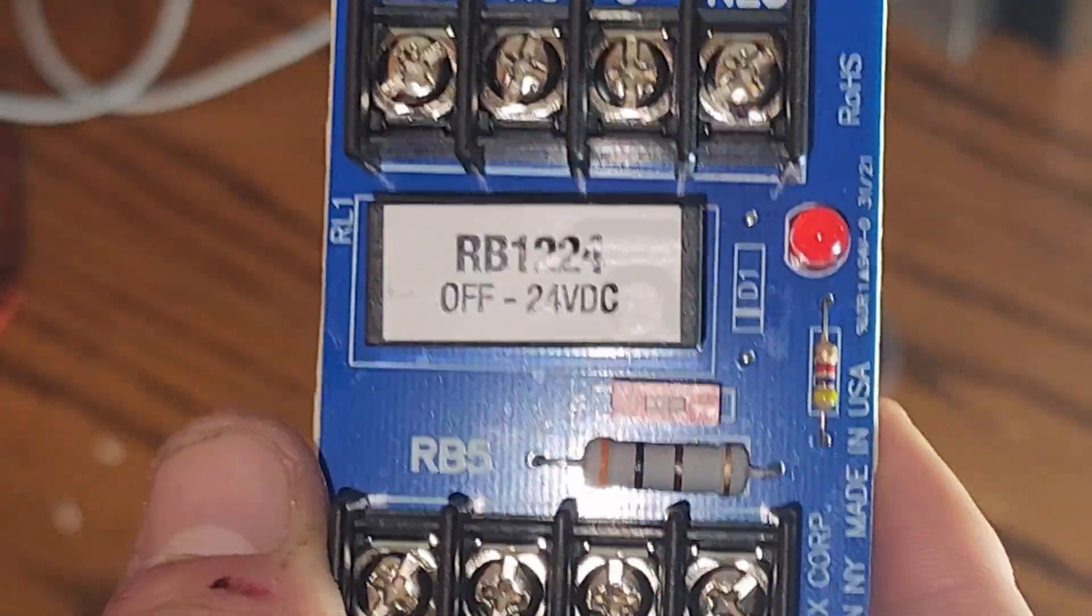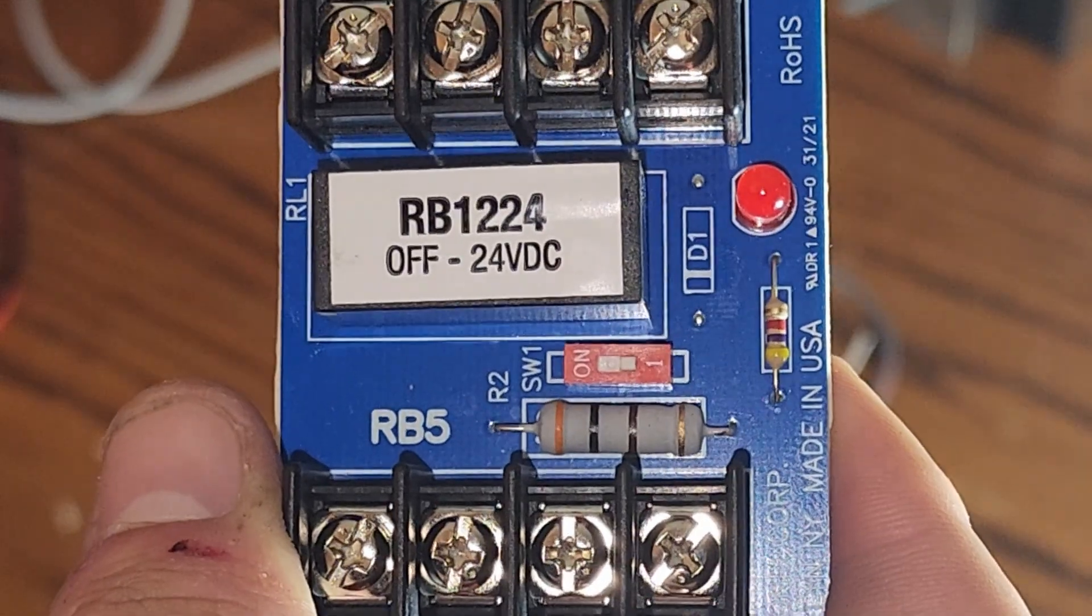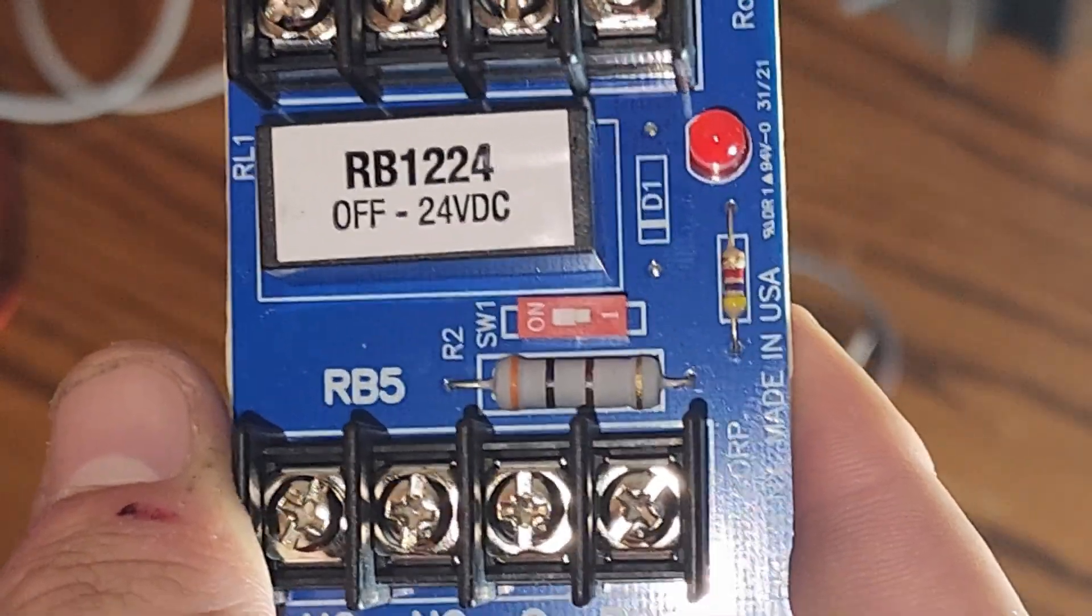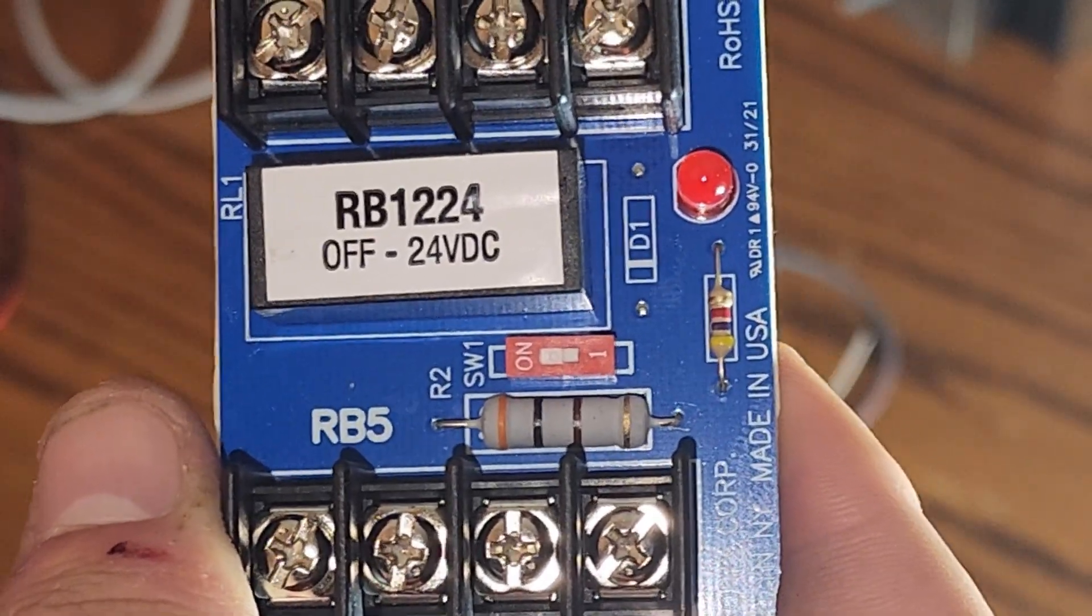Always remember to check this switch when installing a relay. If you have it set to 12 volts and you put 24 in, you will fry the relay.